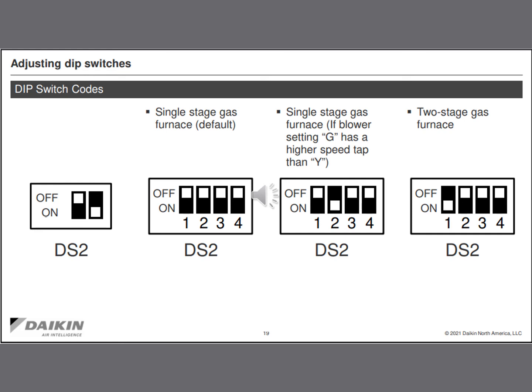If you're using a single stage gas furnace and your continuous fan or your G setting is a higher speed tap than Y, you're going to want to go ahead and turn dip switch number 2 on. And if you have a 2-stage gas furnace, you're going to want to turn dip switch number 1 to the on position.